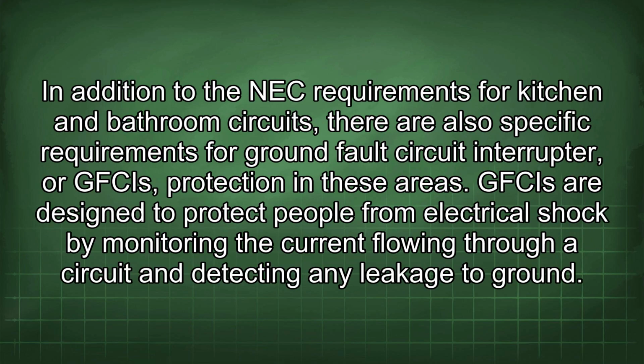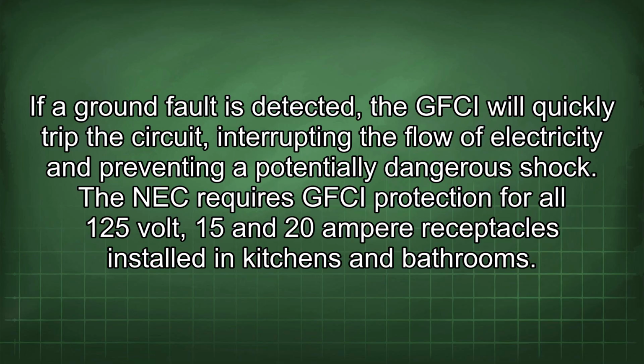In addition to the NEC requirements for kitchen and bathroom circuits, there are also specific requirements for ground fault circuit interrupter, or GFCI, protection in these areas. GFCIs are designed to protect people from electrical shock by monitoring the current flowing through a circuit and detecting any leakage to ground. If a ground fault is detected, the GFCI will quickly trip the circuit, interrupting the flow of electricity and preventing a potentially dangerous shock.